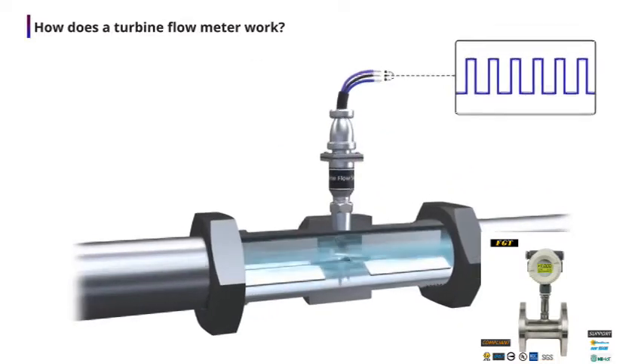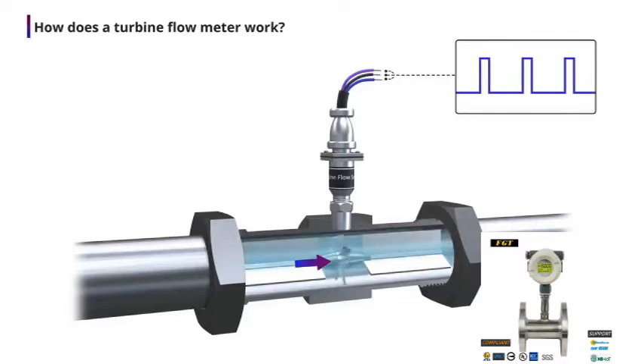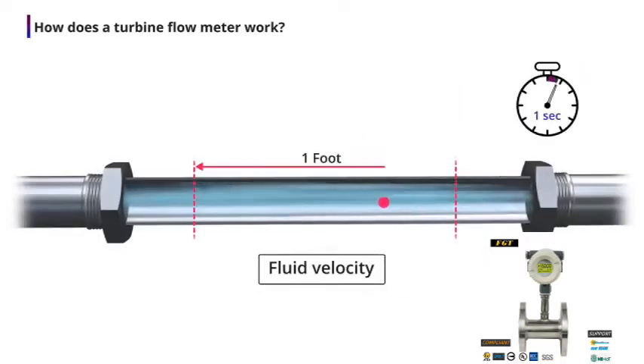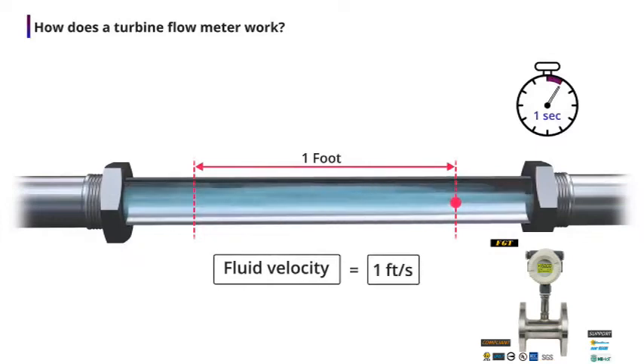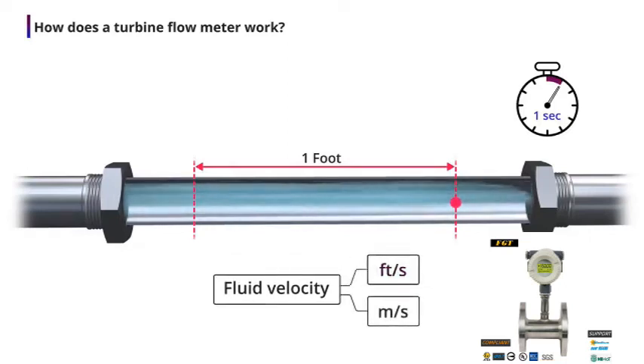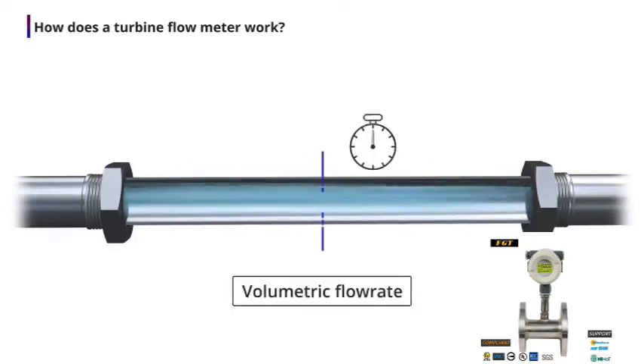As we said earlier, the turbine rotor will turn at a different speed depending upon the fluid flow velocity. Fluid velocity is a measurement of the distance a particle of a substance traveled per unit of time. Typical velocity units are feet per second or meters per second. Fluid velocity plays a very important role in the operation of a turbine flow meter, but in most applications, a turbine flow meter is used to measure volumetric flow rate.